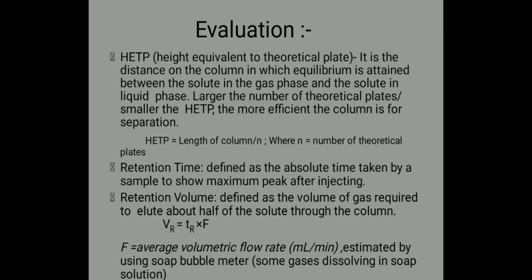Retention time is defined as the absolute time taken by the sample to show maximum peak after injecting. Next we have retention volume. Retention volume is defined as the volume of the gas required to elute about half of the solute through the column. It can be calculated by using the formula VR equals TR times F, where F is the average volumetric flow rate in ml per minute, estimated by using a soap bubble meter. Some gases dissolve in soap solution.